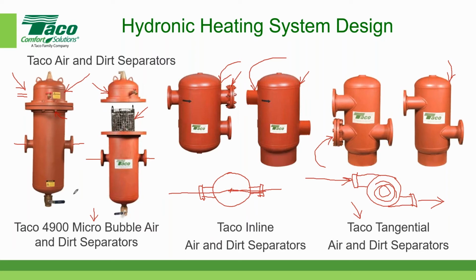Now, the main advantage to the one over here on the left, the Taco 4900 microbubble air and dirt separator, is it doesn't matter what the flow is. So for variable flow systems, which most systems today are, certainly when we're talking about hot water heating systems or hydronic heating, there are variable flow systems, either primary-secondary flow systems or variable primary flow. And these air and dirt separators work well, whether it's at full flow or some percentage of full flow. So perhaps 20% of the full flow, that sort of thing. But the ones way over on the right here become less effective as the velocity drops off because you can't maintain that vortex of the spinning to get the air and dirt to fall out.